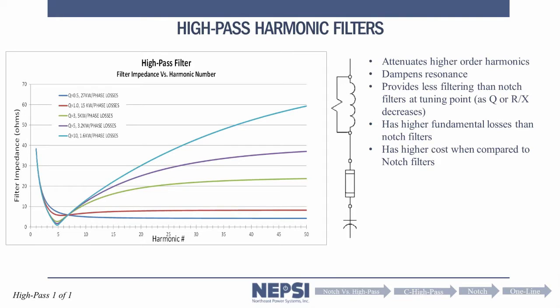The other places you would see it is in wind farm applications, where you're trying to heavily damp the harmonic filter to get rid of a resonance, like cable resonance. So by putting a very low value of resistance into that filter, you get a lot more damping and a lot more impact at higher frequencies, but you get a lot of losses. So one way to avoid those losses is to put a C high pass filter in.